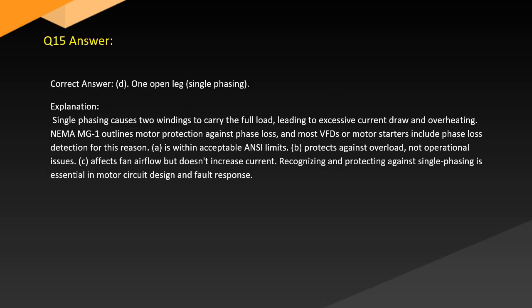Answer. Correct answer D. One open leg single phasing. Explanation. Single phasing causes two windings to carry the full load, leading to excessive current draw and overheating. NEMA MG1 outlines motor protection against phase loss, and most VFDs or motor starters include phase loss detection for this reason. A is within acceptable ANSI limits. B protects against overload, not operational issues. C affects fan airflow but doesn't increase current. Recognizing and protecting against single phasing is essential in motor circuit design and fault response.